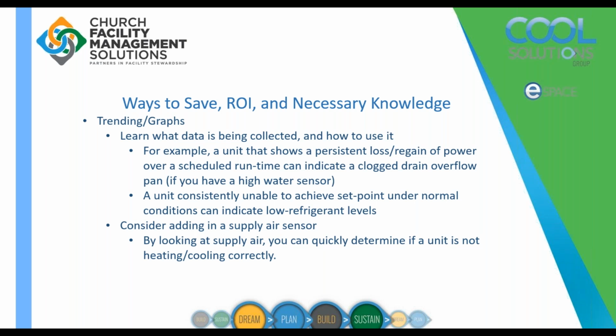Many of the Wi-Fi stats that are available will have at least one sensor input available. Many don't, but I do want to stress it's a great sensor to consider, and that is the supply air sensor. Many times you just drill a hole just past the blower and the coil in the duct, stick in a probe sensor, seal it up, and run it back to that thermostat. What that does is now we can tell what the leaving air temperature is at the point that it's supposed to achieve the greatest cooling or heating level.